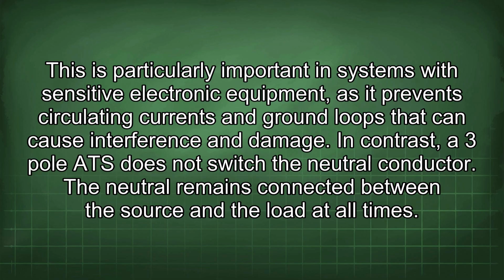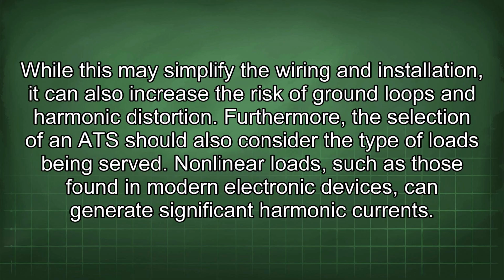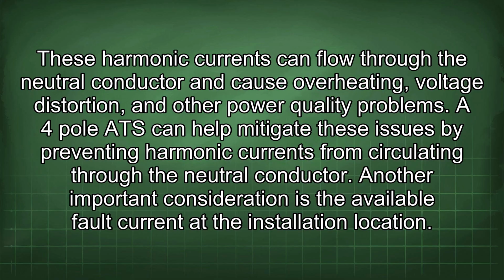In contrast, a 3-pole ATS does not switch the neutral conductor. The neutral remains connected between the source and the load at all times. While this may simplify the wiring and installation, it can also increase the risk of ground loops and harmonic distortion. Furthermore, the selection of an ATS should also consider the type of loads being served. Nonlinear loads, such as those found in modern electronic devices, can generate significant harmonic currents. These harmonic currents can flow through the neutral conductor and cause overheating, voltage distortion, and other power quality problems.